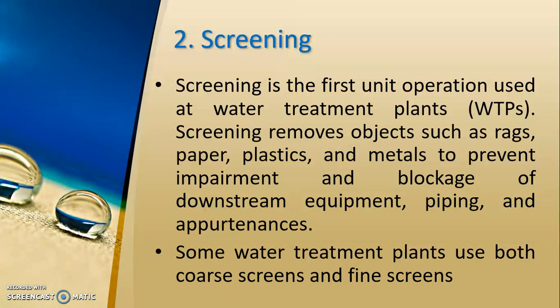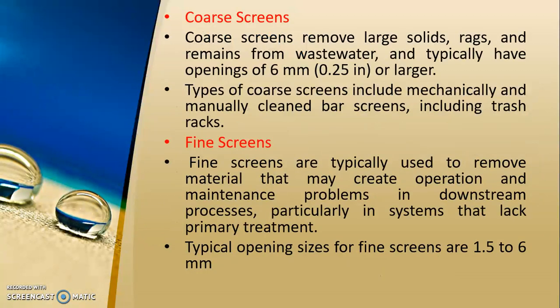Next is screening. When water reaches the water treatment plant, the first unit process it undergoes is screening. Screening removes objects such as rags, paper, plastics, and metals to prevent blockage of downstream equipment, piping, and appurtenances. Water treatment plants use both coarse screens and fine screens — coarse screens remove large size particles and fine screens remove comparatively smaller size particles. Coarse screens remove large solid debris and typically have openings of 6 mm or larger. Types of coarse screens include mechanically and manually cleaned bar screens, also called trash racks.